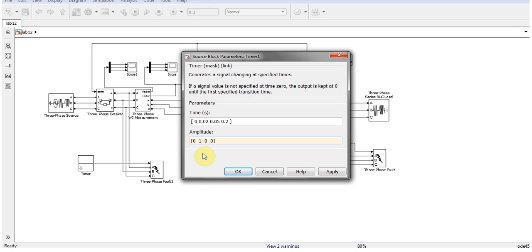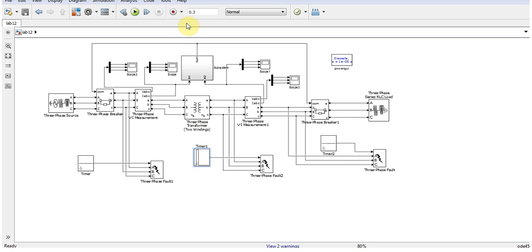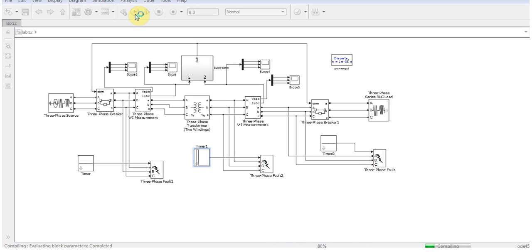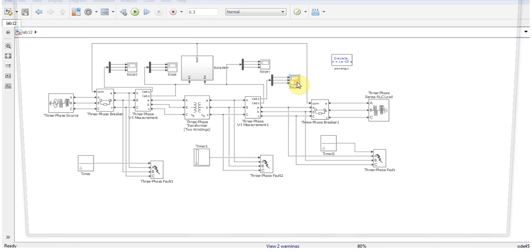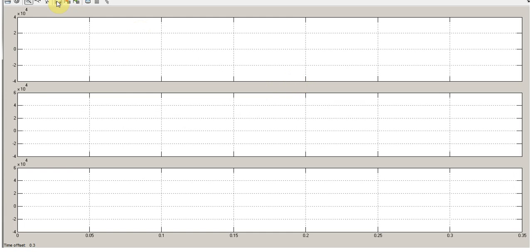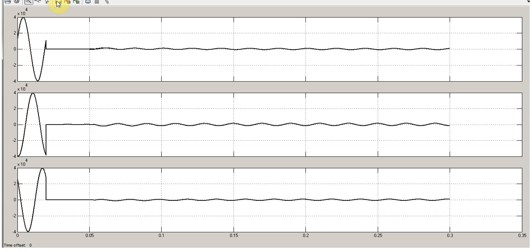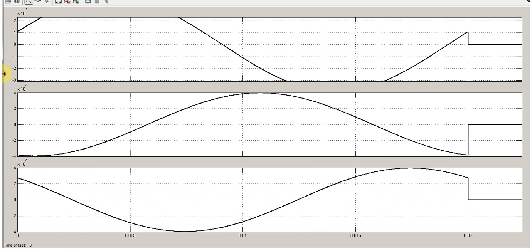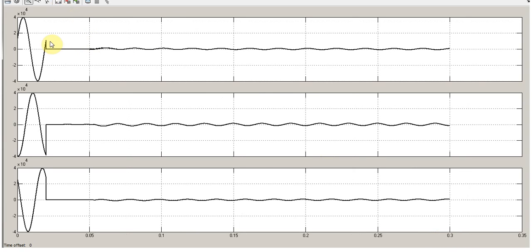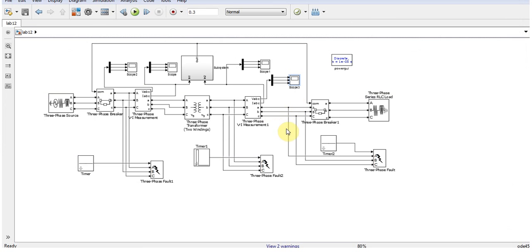Then again, run the simulation. Now let's open the current scope. I will see as the fault is occurred at 0.02, the relay operated and there is no output current passing through the transformer.